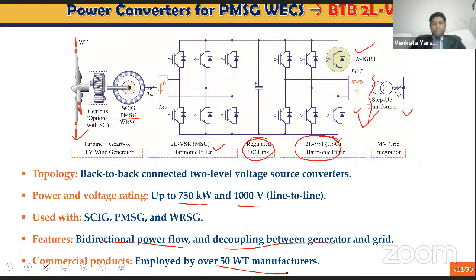If the power rating of the turbine increases over 750 kilowatts, we can increase the power rating by connecting the converters in parallel. Whatever converter we saw before is one converter here, and by connecting more converters in parallel, we increase the power rating. This configuration is used up to 10 megawatts, still at low voltage, that is 1000 volts. The features of these parallel converters are that they are modular, so we can connect as many converters as we need. It is redundant, so if one converter fails, the system can still work with the remaining converters. We don't need to shut down the turbine, and they are more reliable. This configuration is employed by over 40 wind turbine manufacturers.